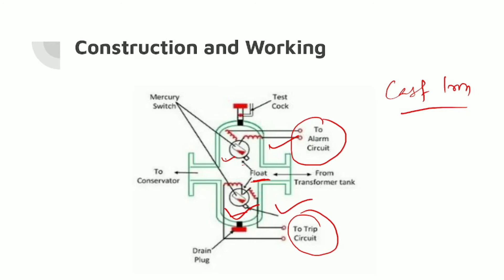There is a pet cock and test cock. The gas trapped in the Buchholz Relay can be released from this pet cock. The relay chamber is also provided with a glass window through which the quantity and the color of the gas can be seen.